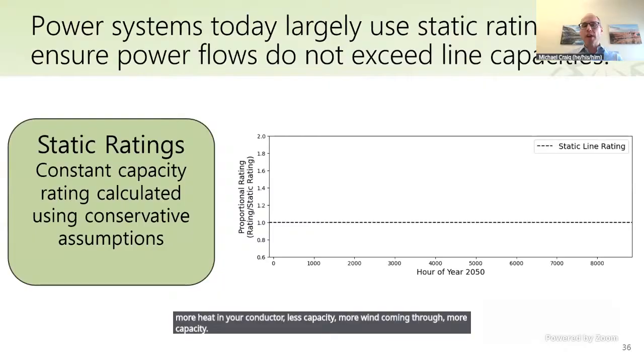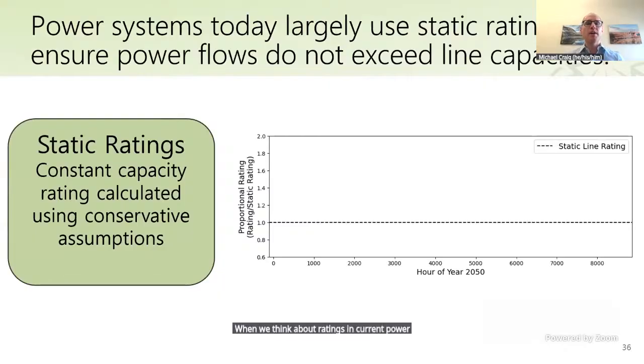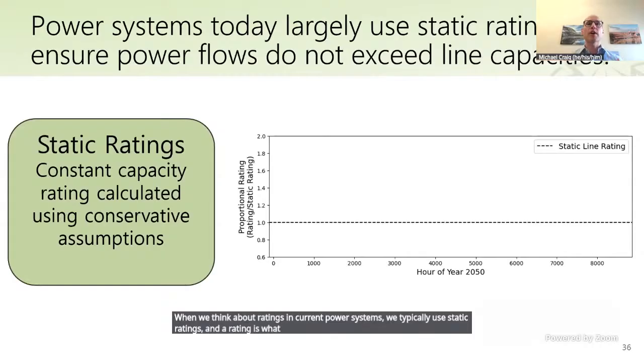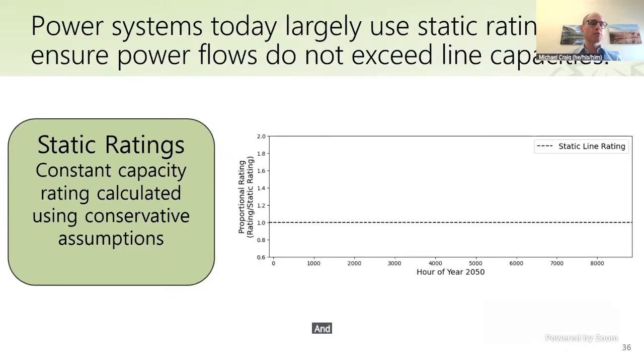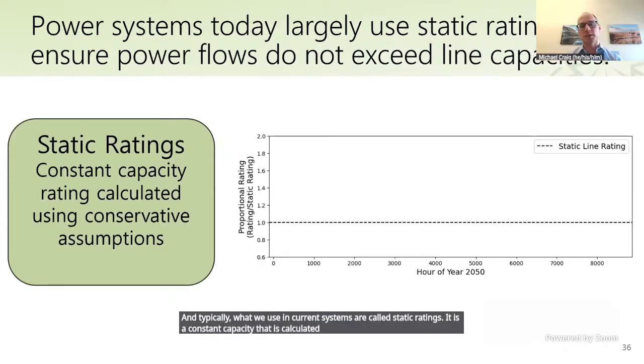When we think about ratings in current power systems, we typically use static ratings. A rating is what the system operator tries to keep power flows below, while capacity is how much could possibly move through the line. Static ratings are a constant capacity calculated using conservative assumptions.